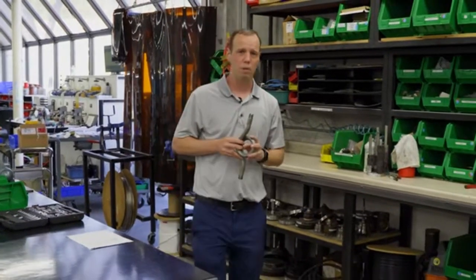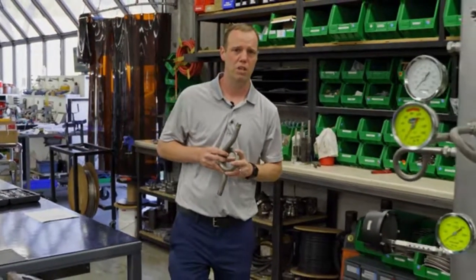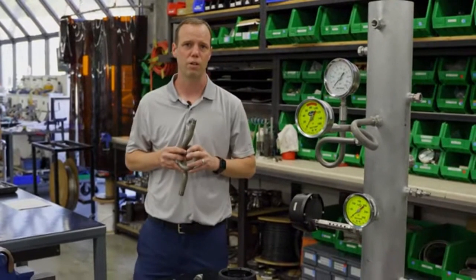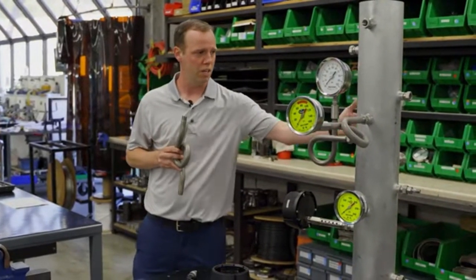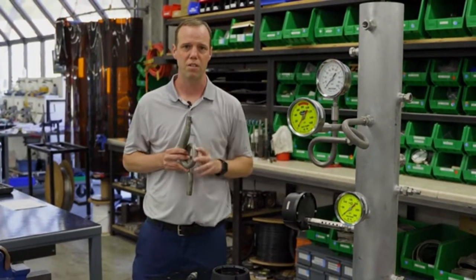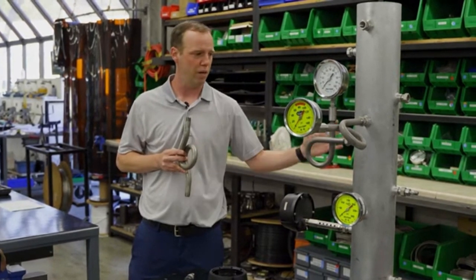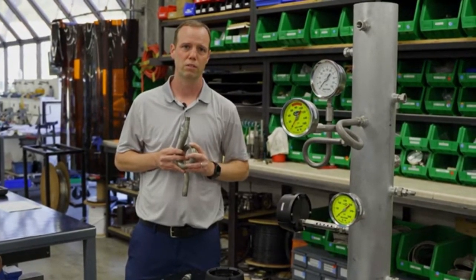Absolutely. Though you may not see the temperature reduction as you would see with a siphon installed in a steam application, it is a valid option to extend the instrument away from the process and to allow ambient air to cool the process.